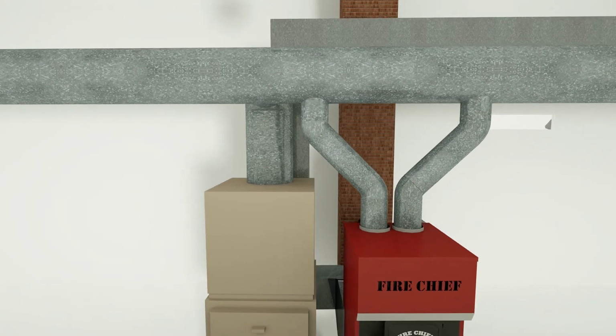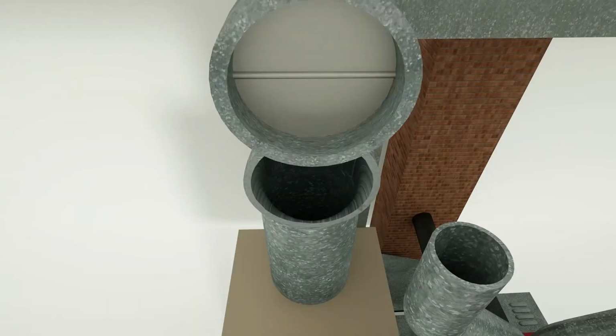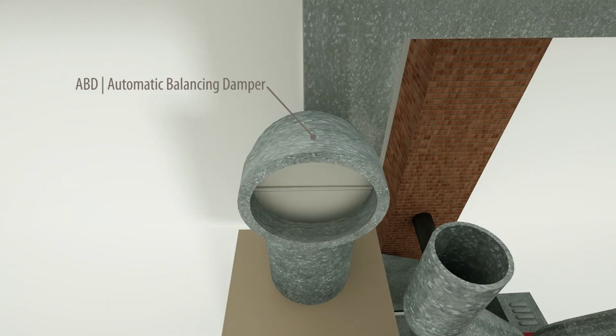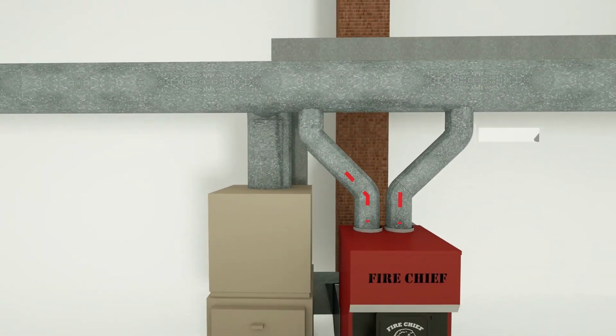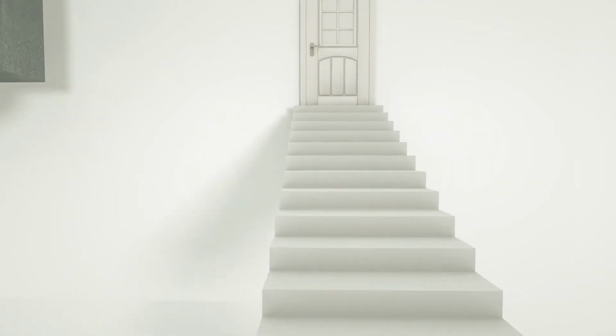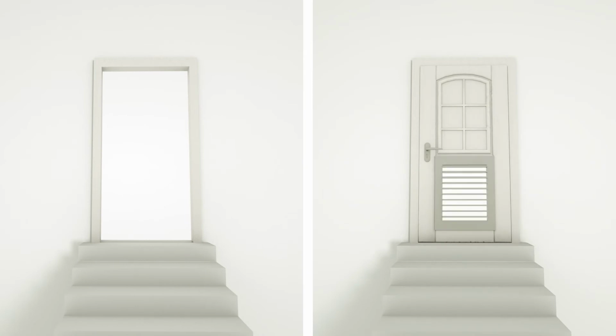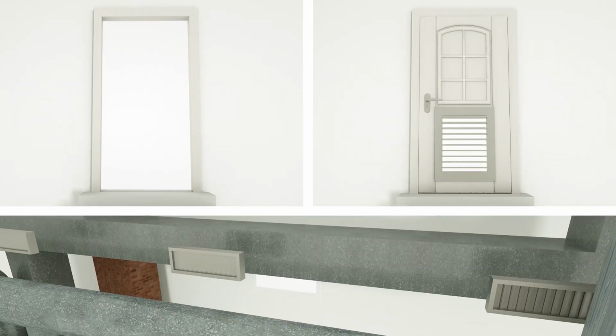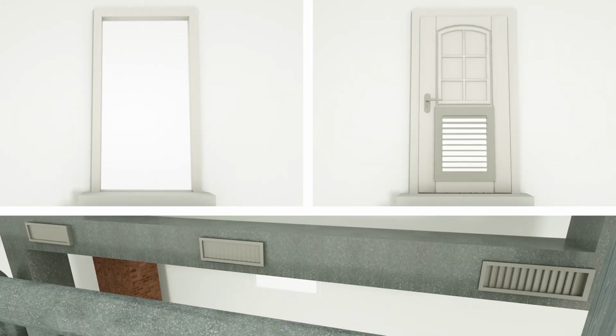To prevent this situation, install a damper in the duct between the existing furnace and the duct connection of the distribution air. Another option to provide return air is to draw air from the location where the furnace is installed, typically a basement. This can be accomplished by leaving a basement door open, installing louvers into the basement door, or installing vent registers in the return air duct within the basement. The vents can be opened in the winter months, but should be closed during the summer to ensure the proper operation of your central air conditioning system.